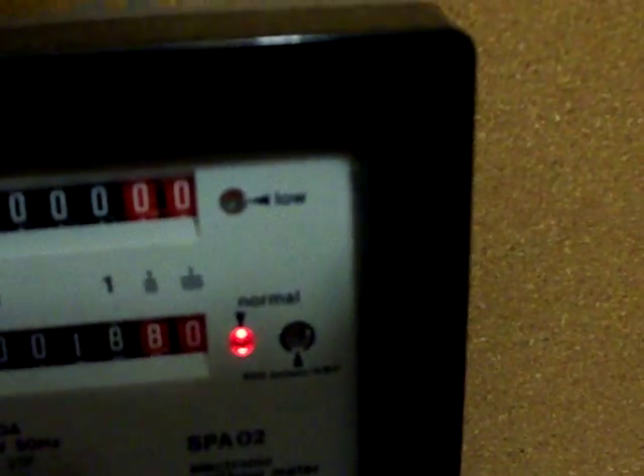It is currently wired up and it is about to go for its accuracy test. The way it works is that it is currently on the .5, and I shall do a test. If that metre advances on to .6 and this instrument here advances on to 18.9, then the other metre — this is the one being tested — will have passed. So it's all wired up and ready to go.